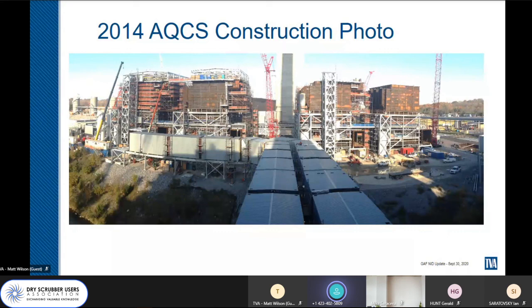So TVA historically has used Cor-Ten, which used to be ASTM A242, weathering steel. They no longer make that. So we did specify ASTM A588, weathering steel construction. So it's basically a carbon steel product, but it has additional chemistry in it to assist with corrosion-based deterioration. So we were not worried too much about the unexposed steel during the construction.